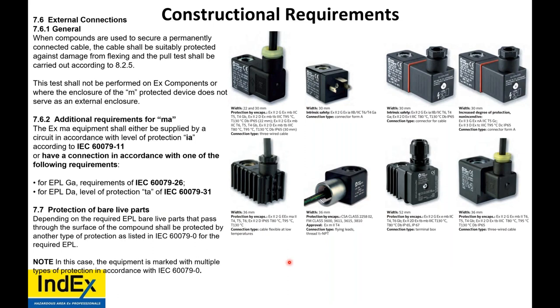Now, protection of live bare parts, depending on the EPL, the live parts, where they pass through the surface of the compound, shall be protected by another means of protection. So these devices, the terminations are made inside of the Ex m. The enclosure is Ex m. It is not another protection technique, but it can go in a zone zero if it's protected by a barrier, Ex i.